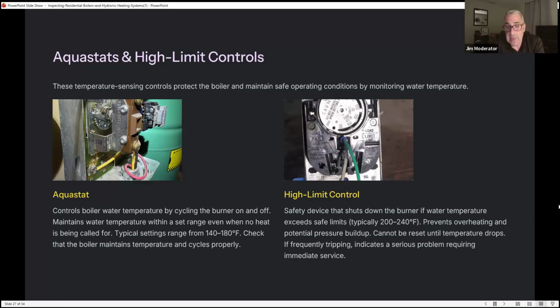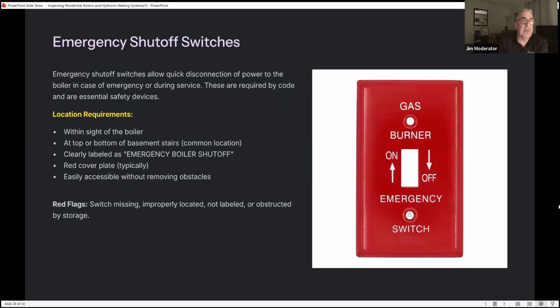High limit control, a safety device that shuts down the burner if the water temperature exceeds safety limits, typically 200 to 240 degrees, prevents overheating and potential pressure buildup. Cannot be reset until temperature drops. If frequently tripping, indicates a serious problem requiring immediate service. So this is just to know what these systems are for newer inspectors.